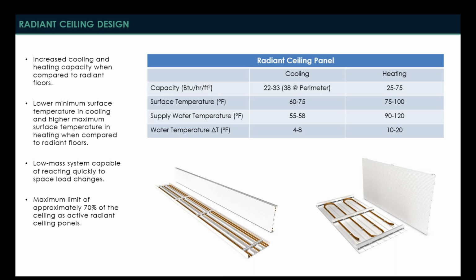And having a high end of around 38 BTUs per hour per square foot at a perimeter is kind of the max that you're going to be able to get, and that would be with a steel radiant panel that has the embedded tubing. So there are a bunch of options there, and there is a bit of a range, and it's very critical that you understand what the loads are in your space to make sure that you're making the right selection.